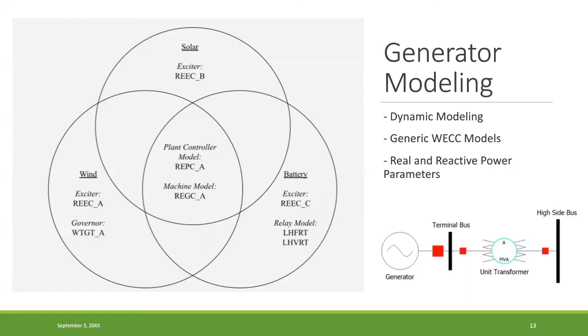Yes, so steady state analysis is the next step in evaluating the system during normal conditions and during contingency conditions. And the reason for that is to ensure a more reliable system as we increase the renewable penetration in California.